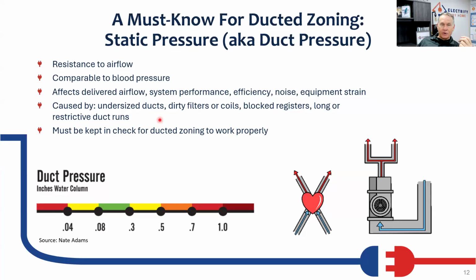Some of the systems that are out there now, there's an EWC system that we've installed a few of. They work pretty good. Pretty good is where I want to just say pretty good. They will actually monitor the static pressure and they will open the secondary damper a little bit to relieve pressure as needed to keep it kind of in the sweet spot. But then we've moved air to the other zone that may not need conditioning. So there's always going to be trade-offs. You just have to understand what the trade-offs are and design around them.